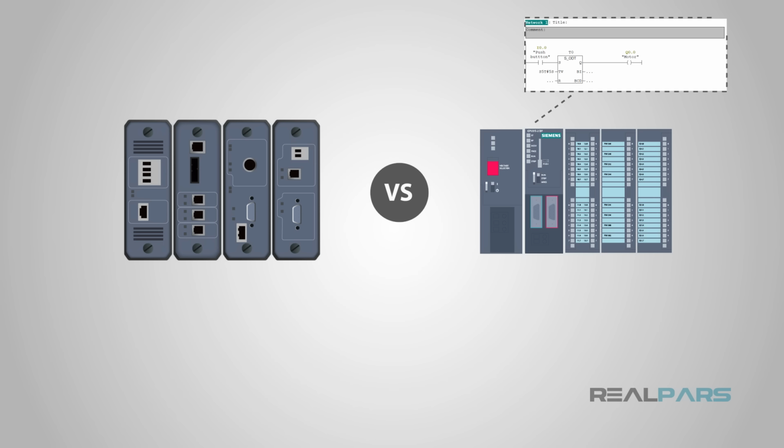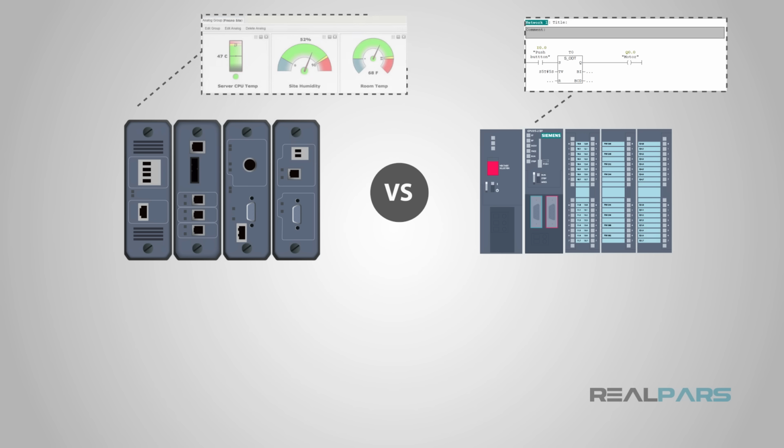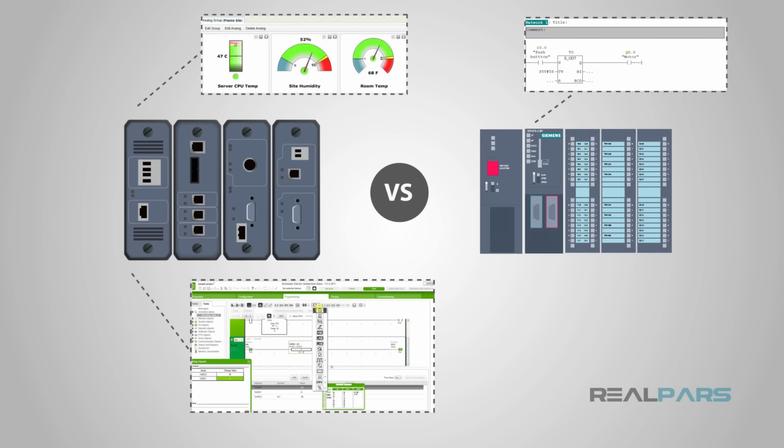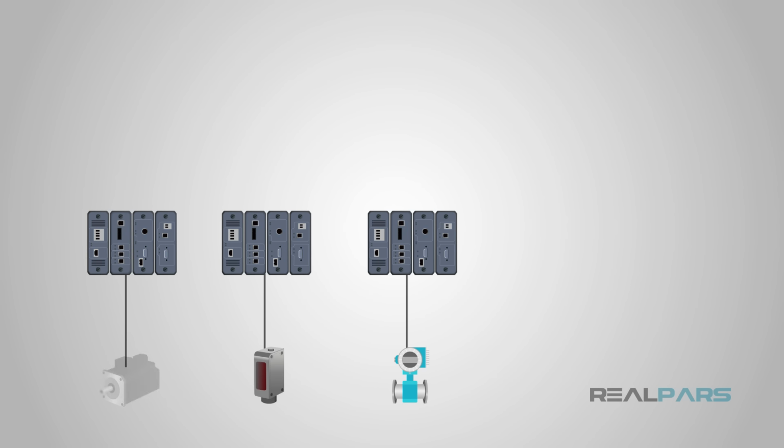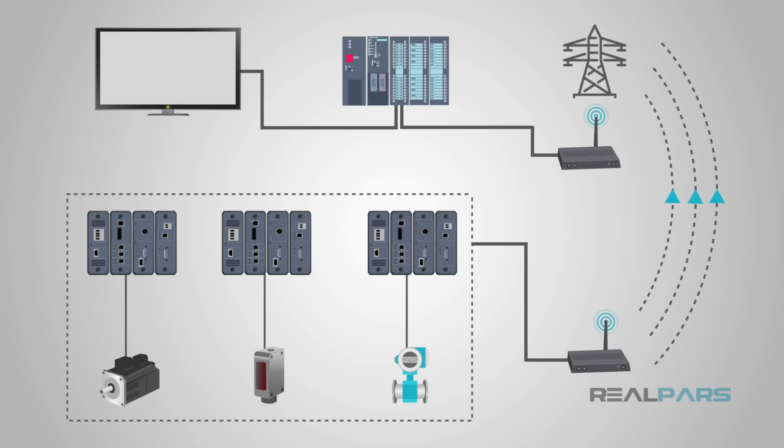A PLC requires specific software and specific skills and knowledge of ladder logic, structured text, function block, etc. An RTU can sometimes be programmed through a simple web interface. In other instances, the RTU comes with setup software that can help you to configure input streams to output streams as well as communications. There are also many RTUs that have pre-programmed modules that can just be applied for the desired function. This advantage can quickly be turned into a disadvantage.